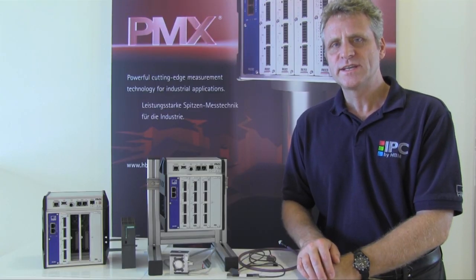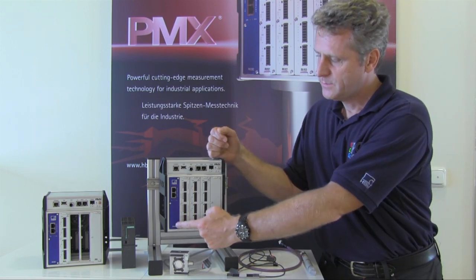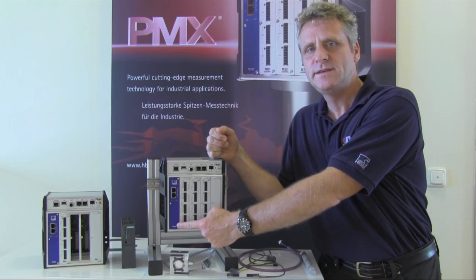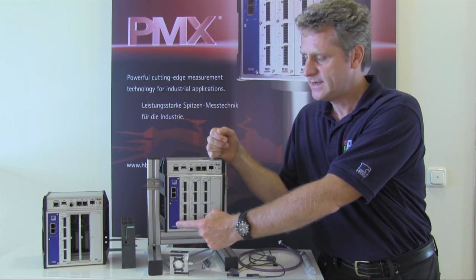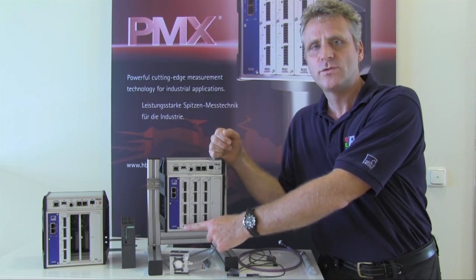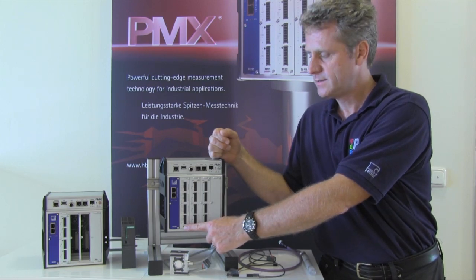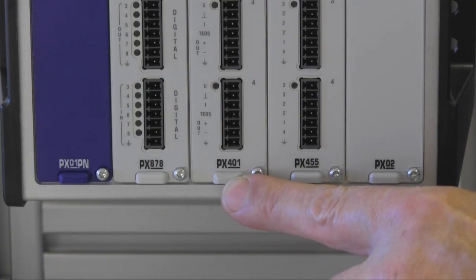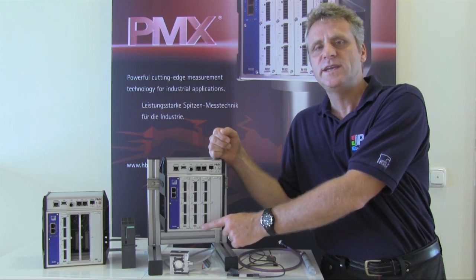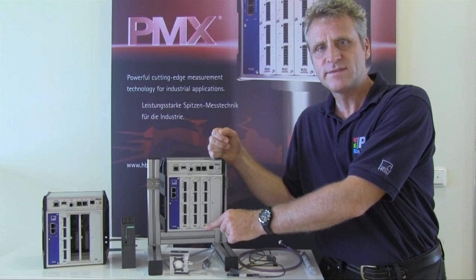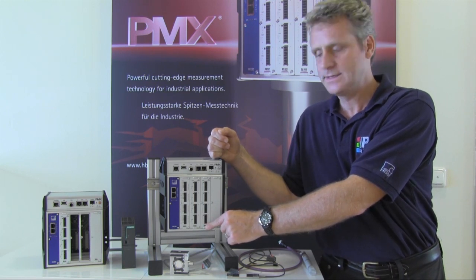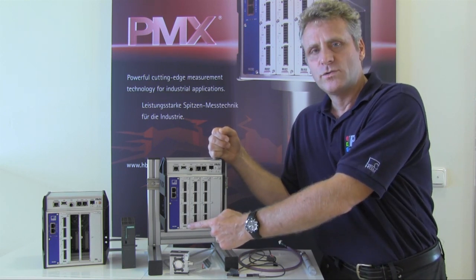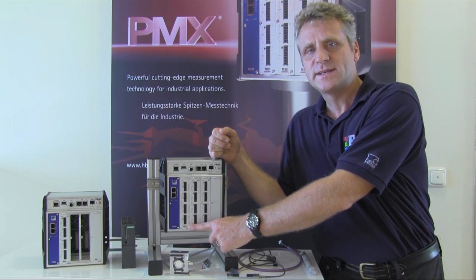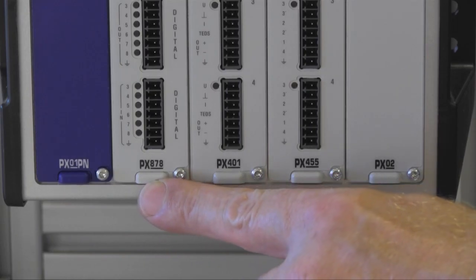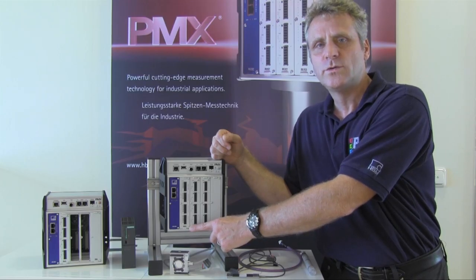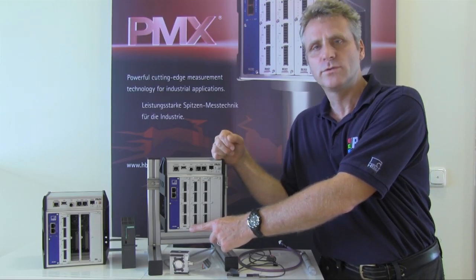The amplifier comes with different plug-in cards. The blue optional field bus card can be obtained as a Profinet or EtherCAT variant. We also have an analog measuring card for current and voltage signals, the PX401. The second card is based on a PX455 4-channel carrier frequency with a sampling rate of 19 kHz. As an analog and digital input-output card, we have the PX878. It provides 8 digital inputs, 8 digital outputs, and 5 analog voltage outputs.